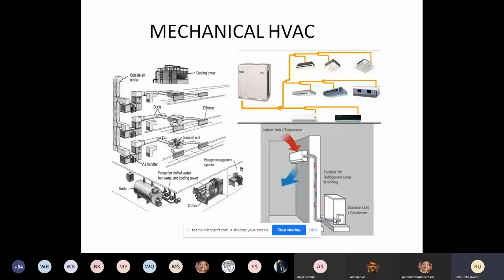Moving to a slightly more evolved form of this split air conditioning system is a VRF system. VRF is variable refrigerant flow. It's very similar to a conventional split system, except that in this case the piping network is the same. So if you can see, there are two different types of high wall units over here. They are both connected to one set of pipes which go to the outdoor unit.